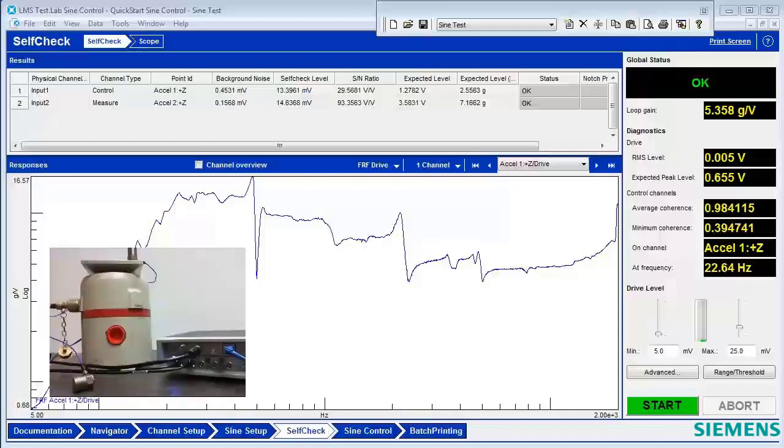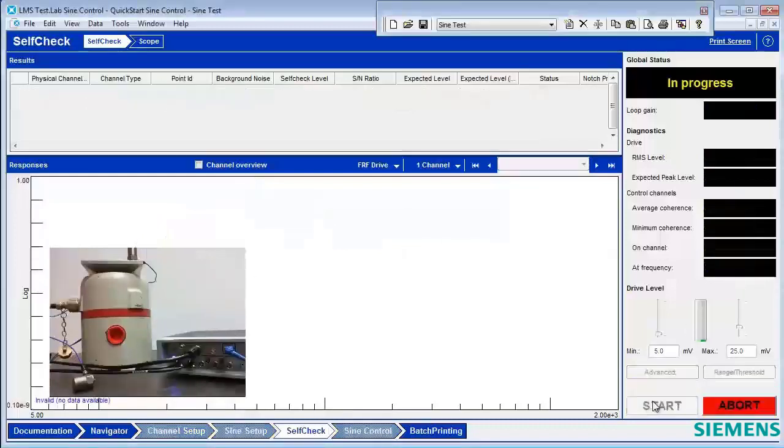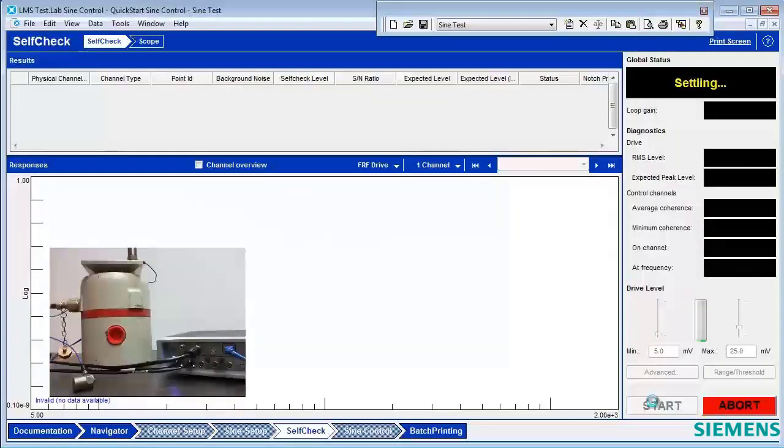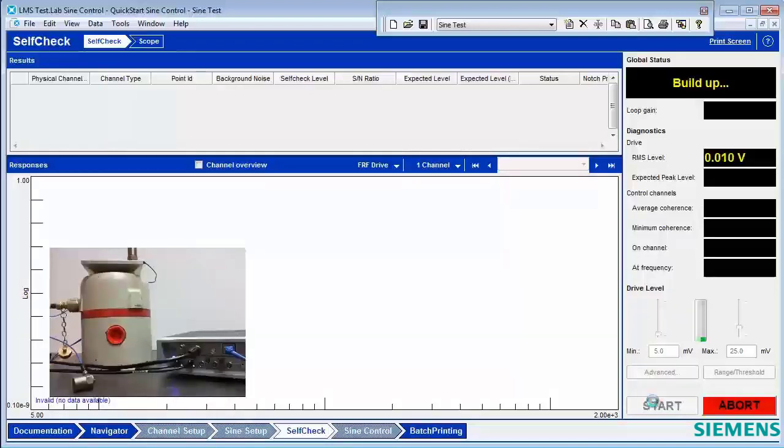To initiate the self-check, you press start, and a low-level broadband signal is sent out to the shaker system. As you can hear now, the levels on all the channels are measured, and based on those levels, you get a report back.